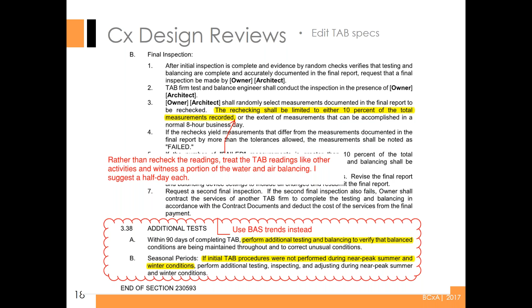Next one is additional testing. Some specs will say perform additional testing, they don't say how much - additional testing 90 days later, or they'll say seasonal periods. With BAS, really, you can get what you want from this by putting in BAS trends. Now this adds scope to the controls guys, but for most of them now it's not a big deal. So I'll suggest that if you do this, it's a whole lot less for you on the back check.